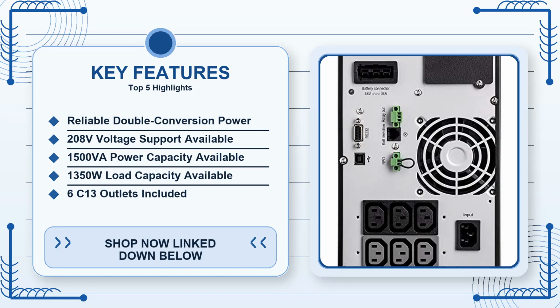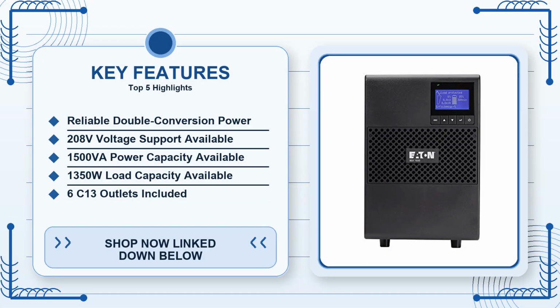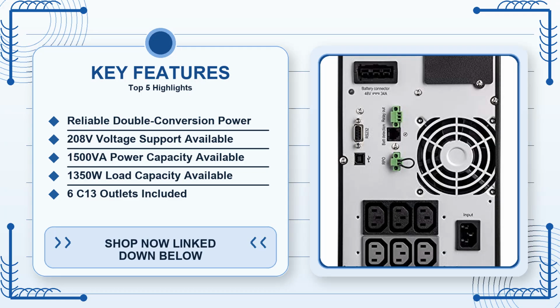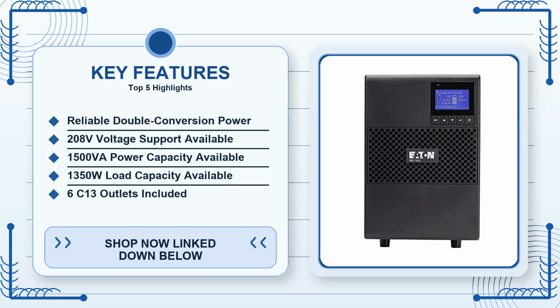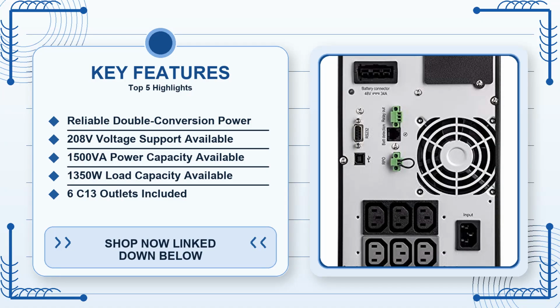EATON designed it with hot swap battery modules, which is a big plus if you plan to service the batteries without shutting down the UPS. In a small server closet, you'll still need to account for a couple of inches of clearance on the front and back to keep airflow optimal. Forgetting this can lead to the UPS's internal temperature climbing, triggering alarms and reducing battery life. So, before you shelve the 9SX, measure that rack space and verify you have the clearance.